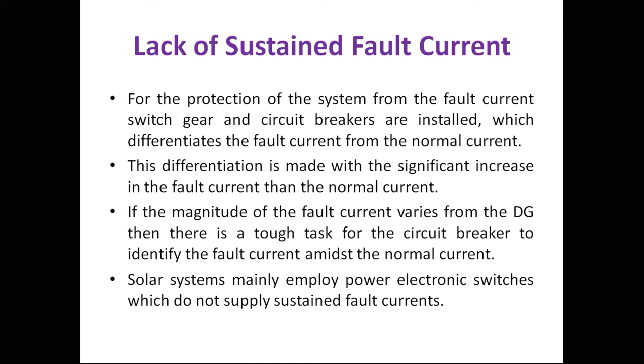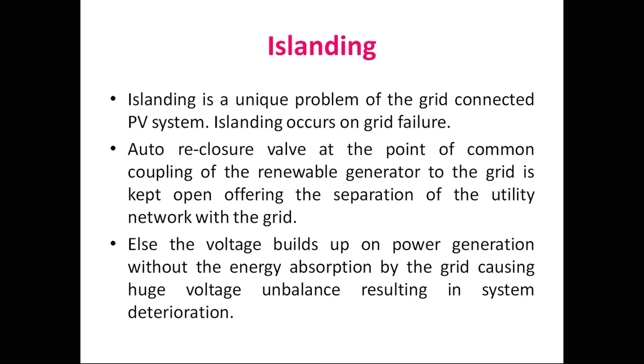Solar systems mainly employ power electronic switches which don't supply a sustained fault current. Power electronics won't give proper current — harmonics cause the active current component to be reduced. This is the core problem with PV systems in terms of lack of sustained fault current protection.